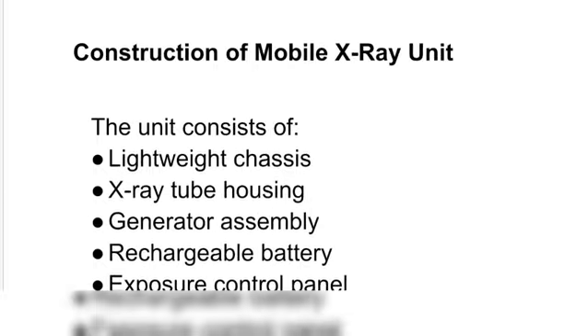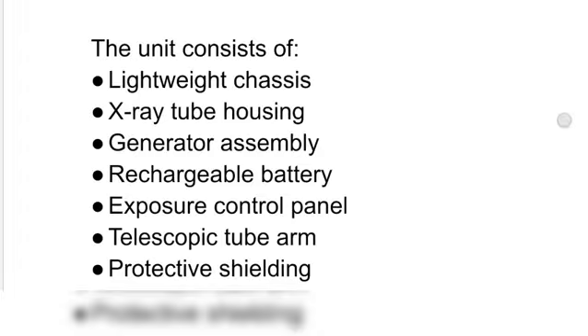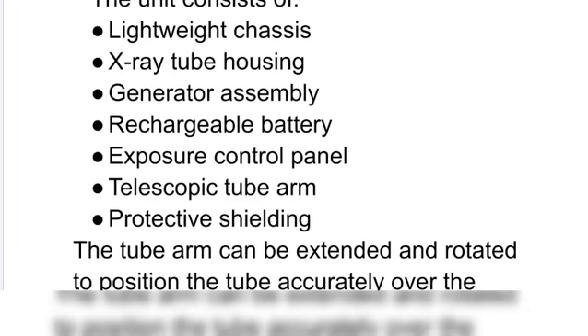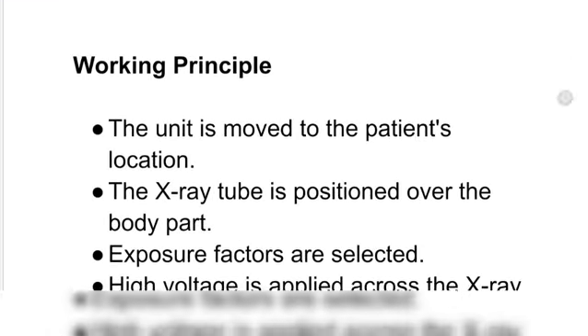Next is the construction. Construction of a mobile X-ray unit. What does the construction consist of? The unit consists of a lightweight chassis, X-ray tube housing, generator assembly, rechargeable batteries, exposure control panel, telescopic tube arm, and protective shielding. Usually, this tube arm can be extended and rotated to position the tube so that it accurately reaches the patient. Next is the working principle.